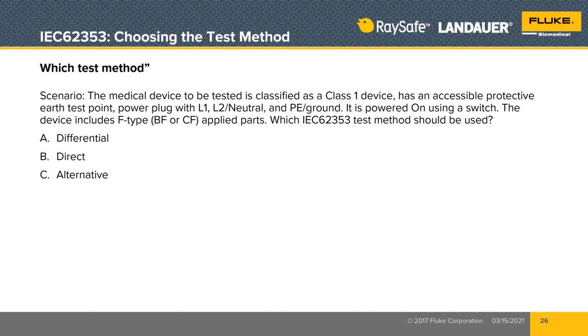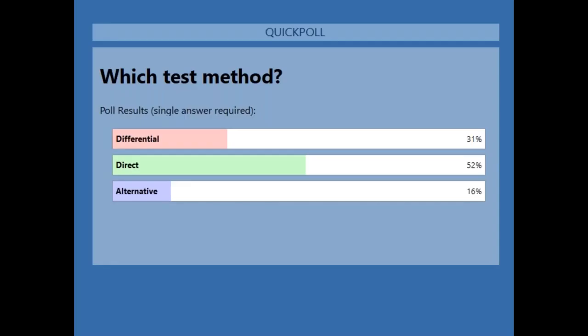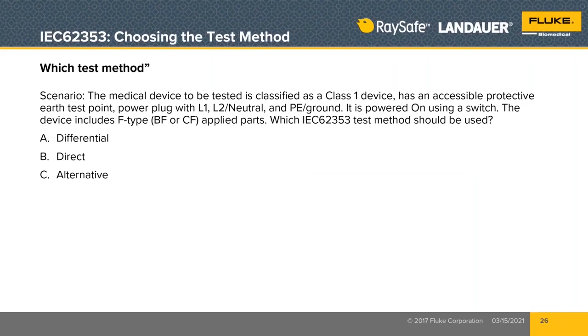Okay, and we'll go ahead and share what the folks had to say. So 52% direct, 31% differential, and 16% alternative. Okay. So here's the big reveal. The answer here we chose is direct, and the reason is because we want the test results to be as much like IEC 60601-1 as we can. And because it has a switch, and because the device applied parts are isolated from protective earth, it should be the direct method. Now, differential could be chosen, that's okay.